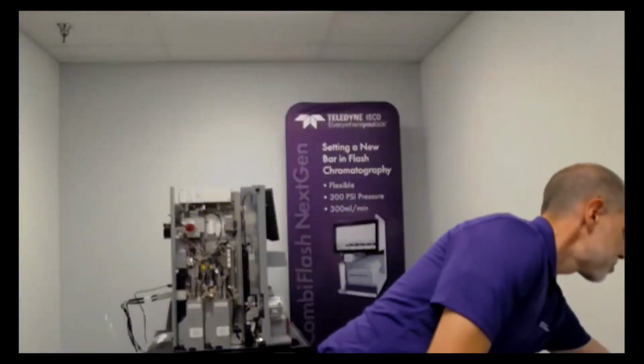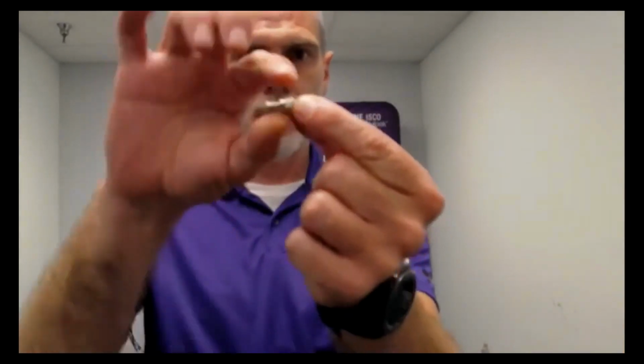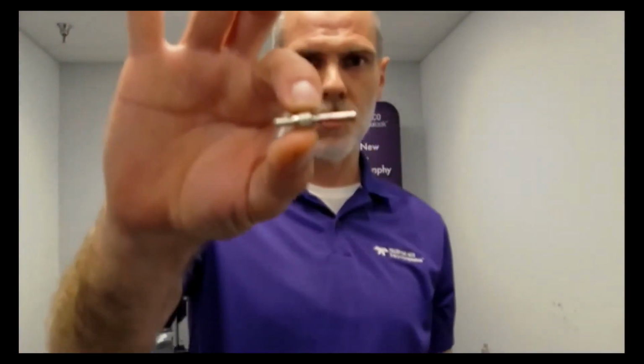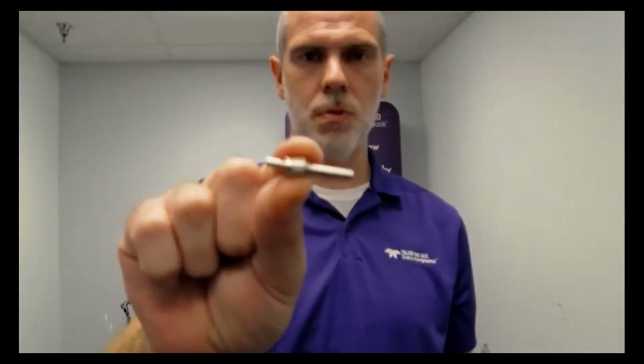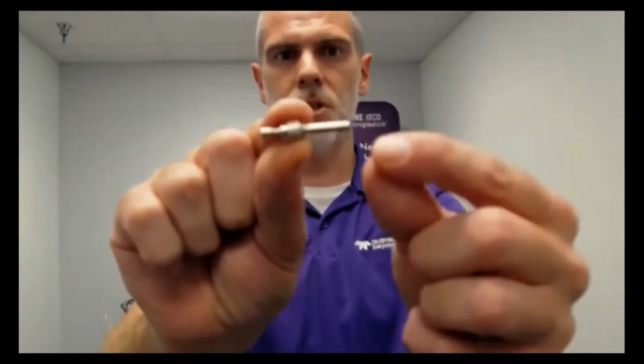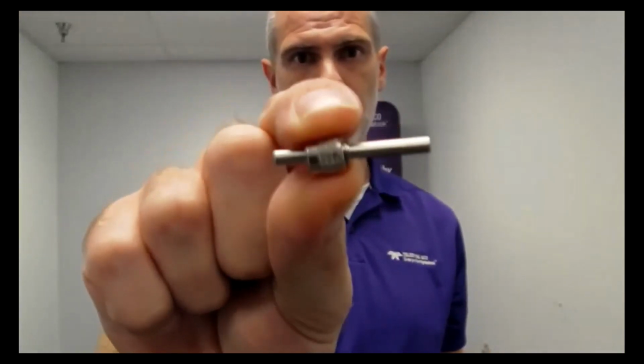And I have another question here from Paul asking, have you seen much in the way of fiber optic failure on the detectors? Yes, yes, we have. I wouldn't say a lot, but I have seen failures. And what I mean by that is, this is the fiber optic rod that I was telling you about here. Kind of see it there. Sometimes this will block your light. So there's a tip there and a tip there that you can dip into methanol and clean with a Kim wipe or some other kind of lint-free wipe. Now, a lot of times that will clear it up and you will get light energy through there again.